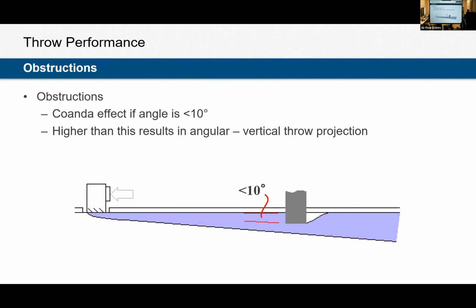Coanda and obstructions. Usually we can design this beautiful ceiling and all of our airflows could work perfectly fine. And then a sprinkler head gets dropped or an exit sign or a lighting fixture. All of these are different obstructions in our ceiling that are going to affect the airflow pattern across the ceiling. If that obstruction creates a greater than 10-degree angle from our airflow jet, then we will have an issue. If we're less than 10 degrees, we won't.